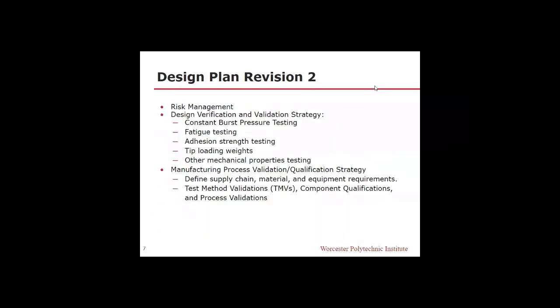For the second revision of the design plan, we added several aspects. First of all, we implemented a risk management or assessment aspect. We will talk about this more in depth later. We also added several design verification and validation strategies. In order to test how much force the balloon can withstand, we will use a constant burst pressure testing. In order to see if the balloon can last the entirety of the operation without failing, we'll utilize a fatigue test that puts the balloon through several cycles of stress.